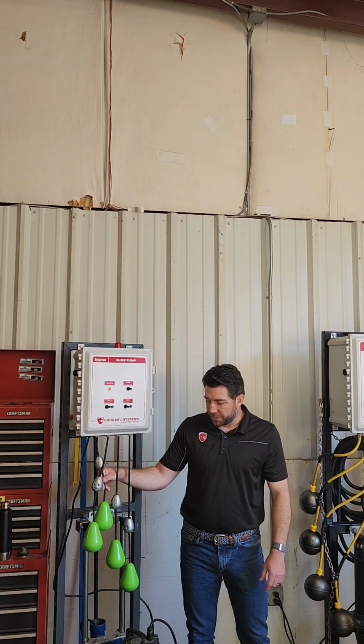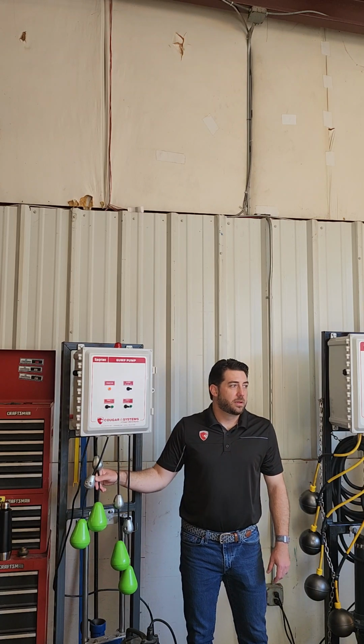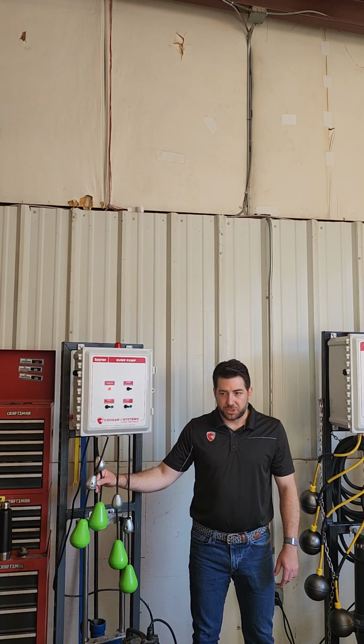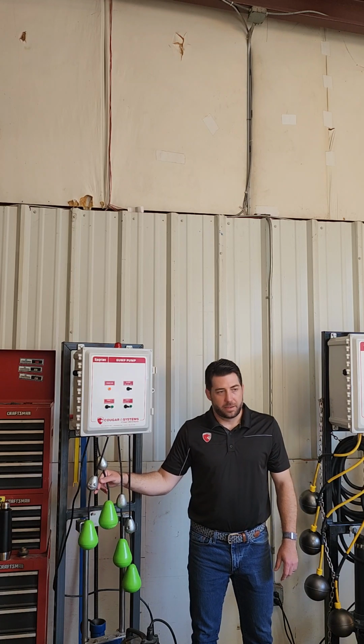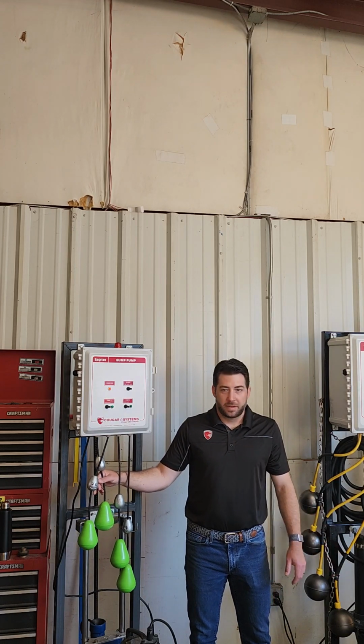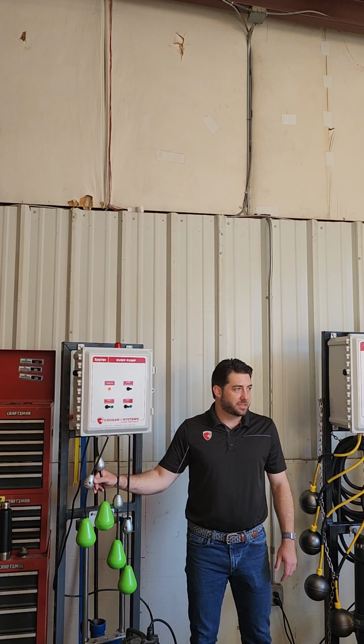Like you said, you can put the high level alarm before the lag pump. So if it's a storm pit and it sometimes can happen that both pumps are going to run, they may see that as a nuisance alarm, right? But it's still good to get.